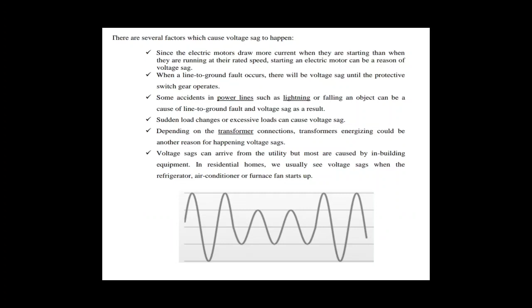You can see the voltage sag is for only 2 cycles here in the sinusoidal waveform. You can see the first cycle is completed and one pulse of the second cycle is totally completed, but the next pulse of the second cycle drops from its nominal value, and these two cycles have voltage sag.